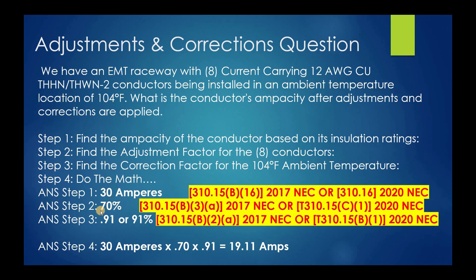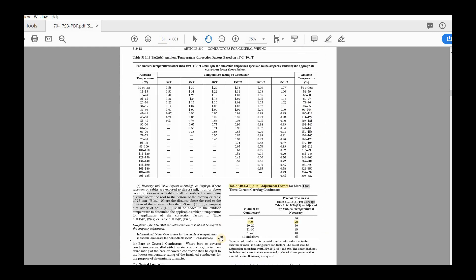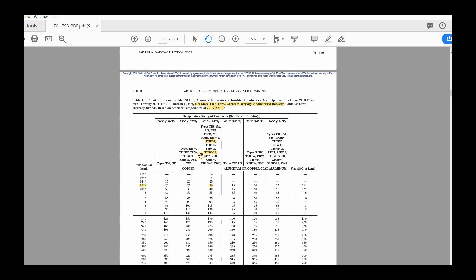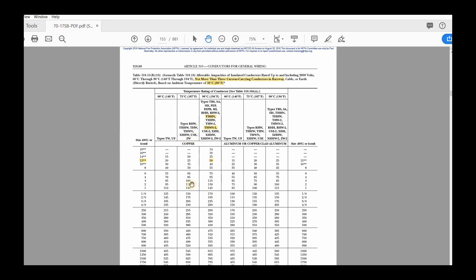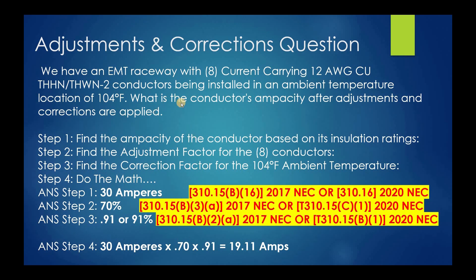Now the next thing is the correction factor for the ambient temperature. In a perfect world we could simply pull the ampacities from the table. Remember, we do have terminal limitations — 75-degree terminals are typically what you'll get, but we can use the 90-degree column for adjustment and corrections. We also want to make sure that at the end of the day we don't exceed the value under the 75-degree C column. The question simply asks: what is the conductor's ampacity after adjustment and correction is applied?